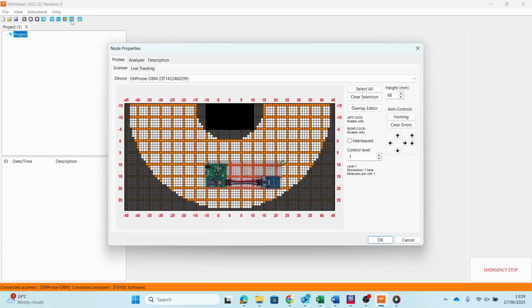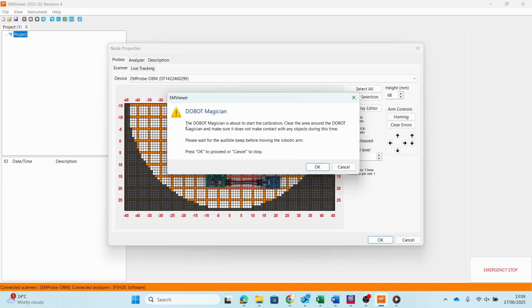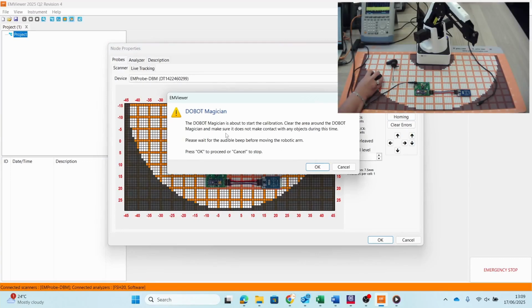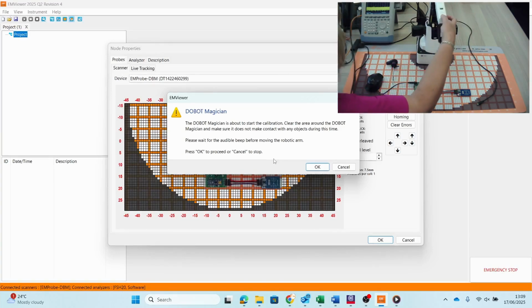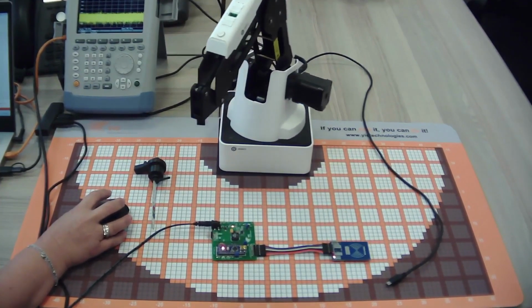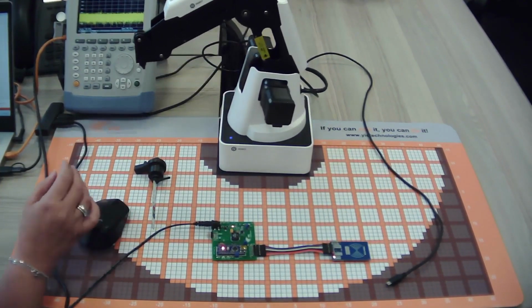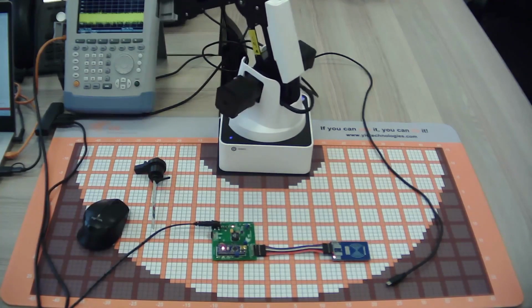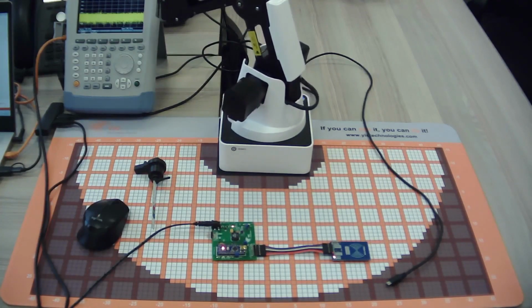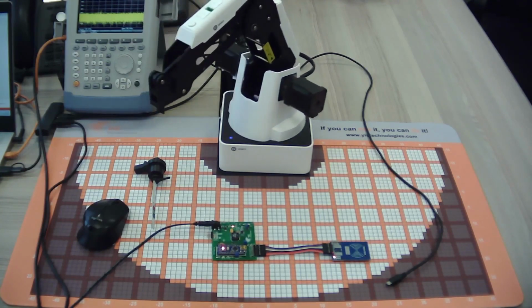The EMProbe must be aligned before use to ensure the arm moves accurately. Click the homing button and then follow the instructions on the screen. It is recommended to perform the homing without any probes attached. During homing, the LED will flash blue. Wait for the beep sound to indicate that homing is complete, and the LED will then turn green.